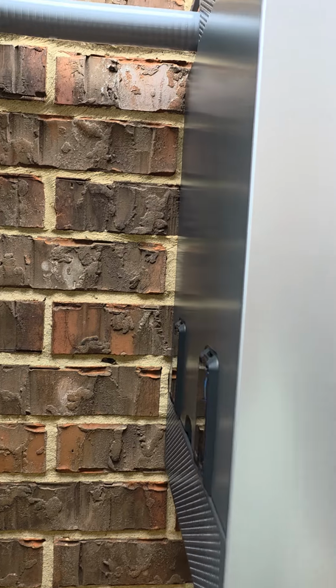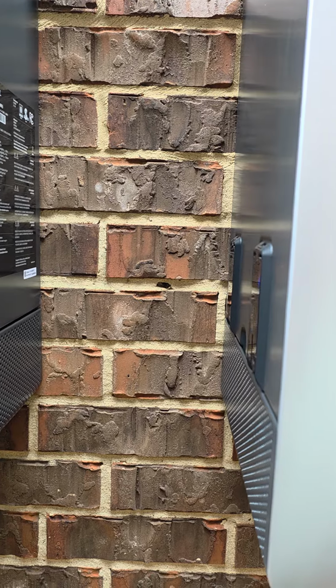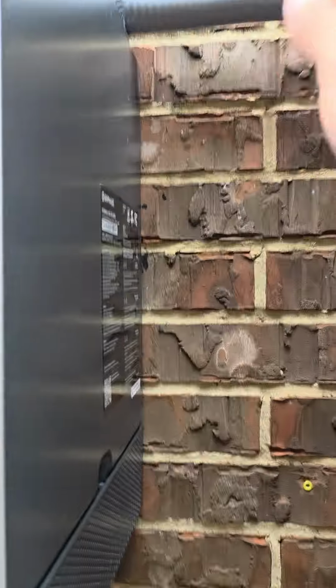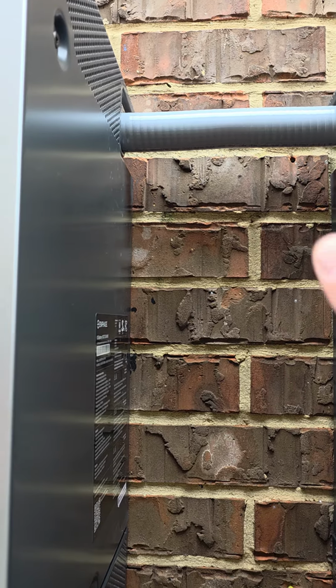And I wanted to utilize the biggest opening possible on this side, because what I did was run one singular conduit all the way through. So basically, for each battery, you have the two lines, the neutral, and the COM cable, and as you get closer, so not an issue here, your wire and the ground, and your wiring is not that big of a deal in a 1 1/4 inch. But when you get past here, now you got double the wiring, right?